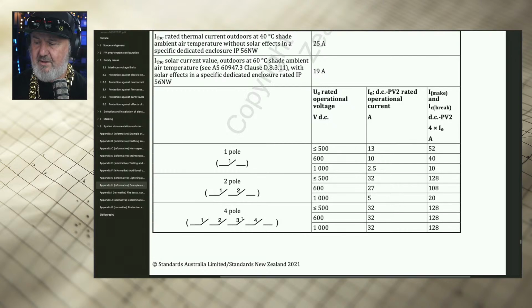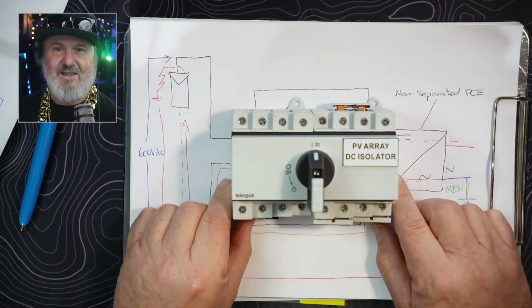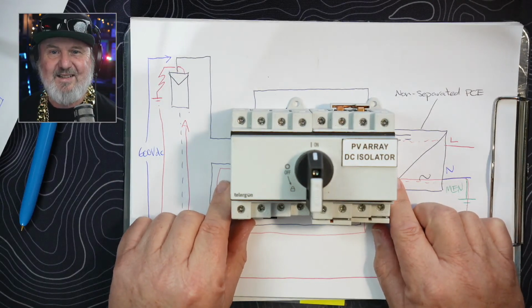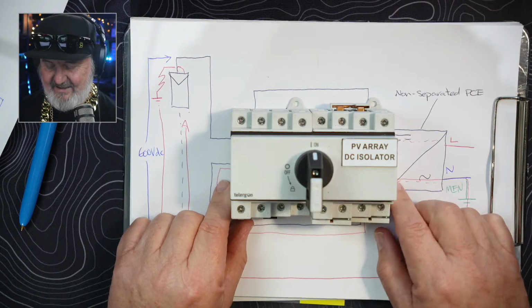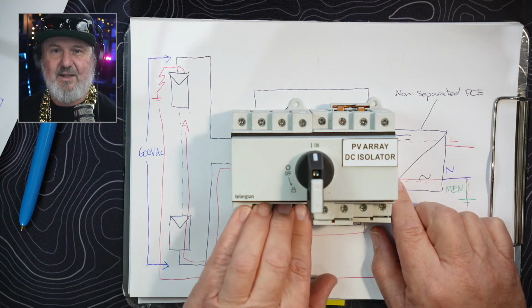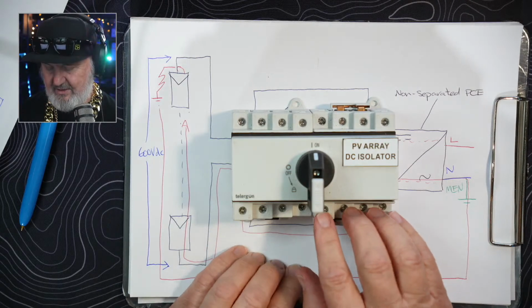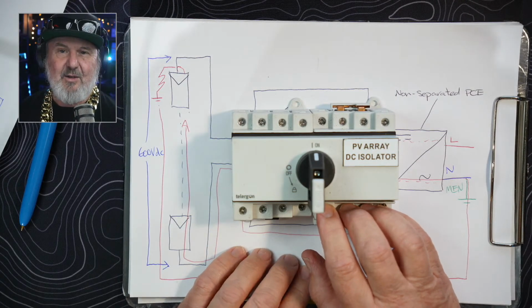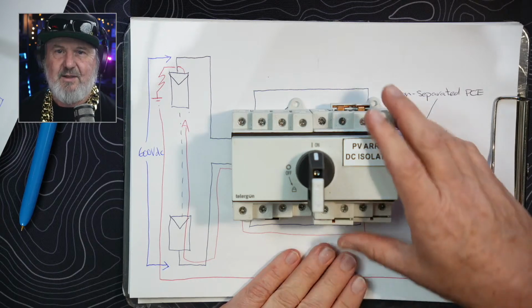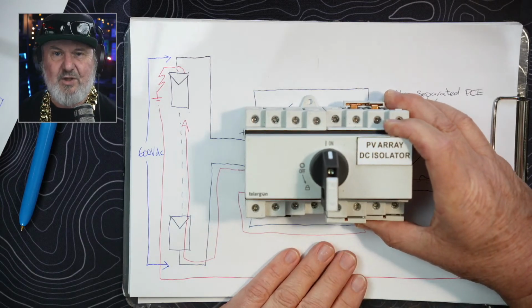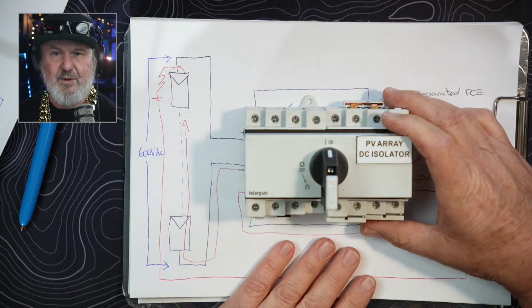You might go, well, 4 poles in series? Well, that could be for a galvanically isolated inverter where it's always going to switch all 4 poles. The current is always passing through all 4 poles. Or it might just be a big mother like this one. There's an 8-pole DC isolator. And on one side, so that's the negative side, 4 poles in series, and the opposite side, another 4 poles in series. So that would also be 4 poles switched under earth fault with a transformerless inverter.